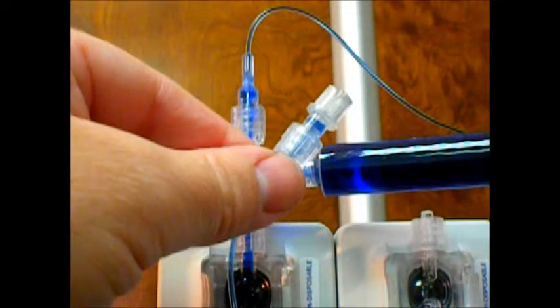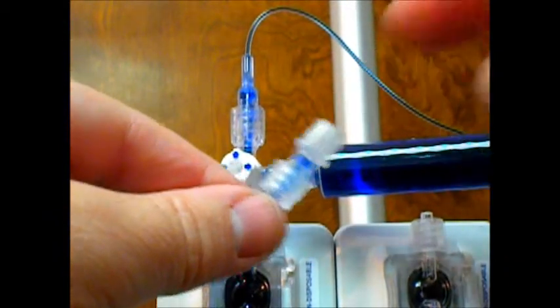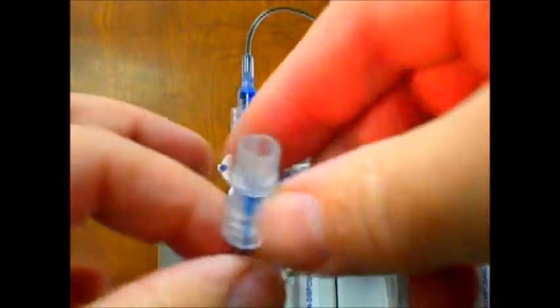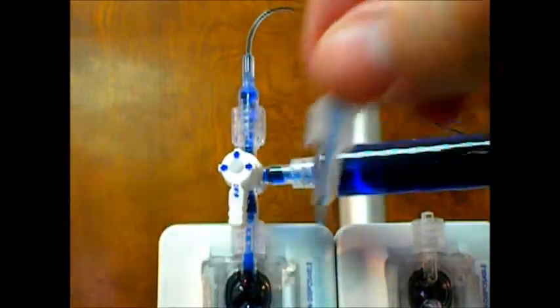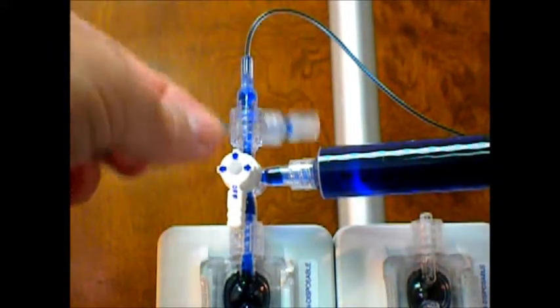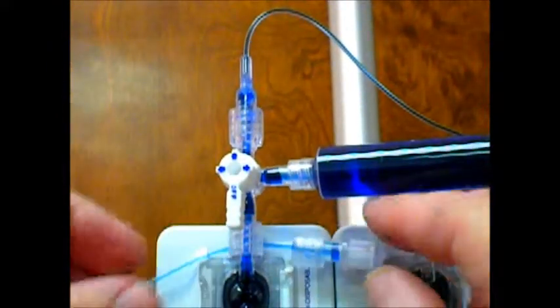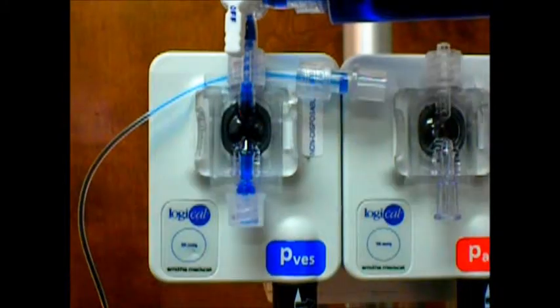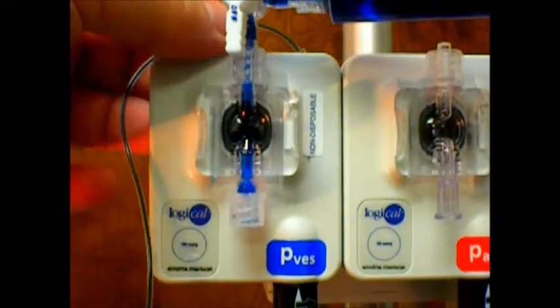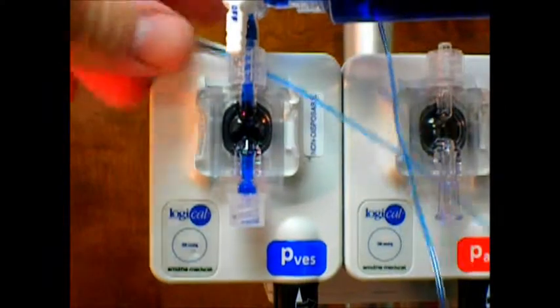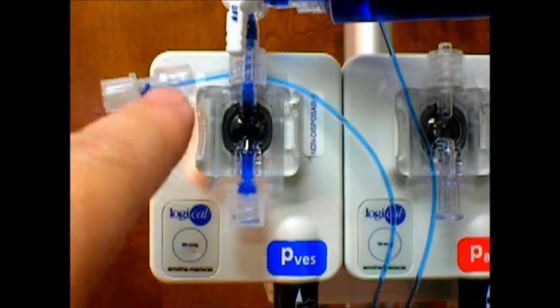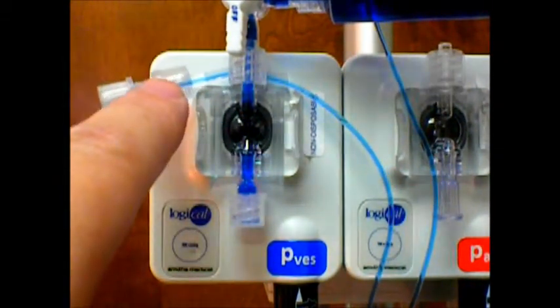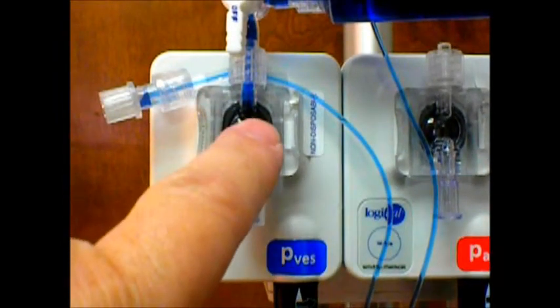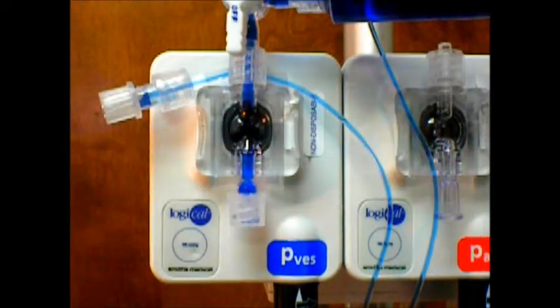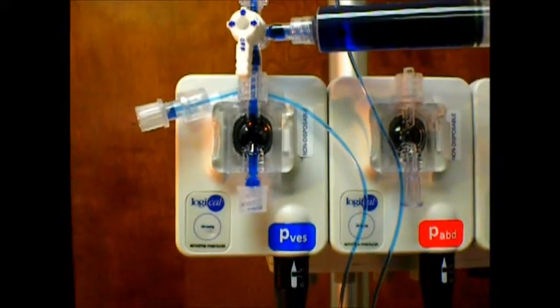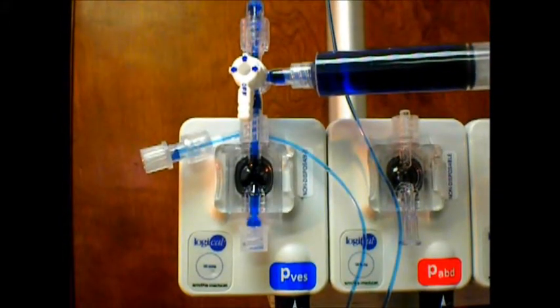Now, again, the Laborie is a little bit different than this, but the principle is the same. The tubing is vented to air, so you don't have to worry about it. Now, the easiest thing that I do is I just lay this tubing over the top of the transducer right here, because that way where the tubing goes to air, it is at the same level of the transducer.